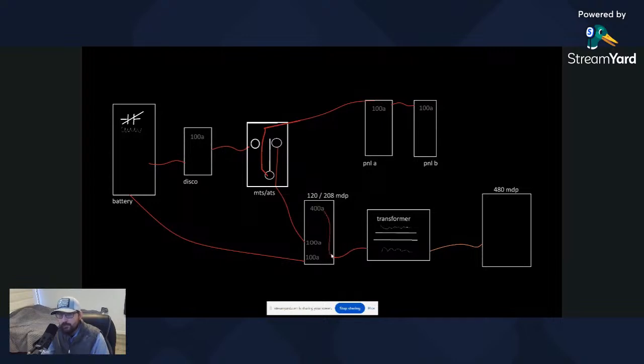Now I'm going to show you a scenario where he was actually okay because the type of wire that he ran and the type of lugs that he had and the breaker was actually 90 degrees C rated. And he was able to use the 90 degree C column, which is pretty rare. So he was actually able to get away with keeping his wire and showing me the lug ratings, which doesn't commonly happen. But anyway, so he was good here.